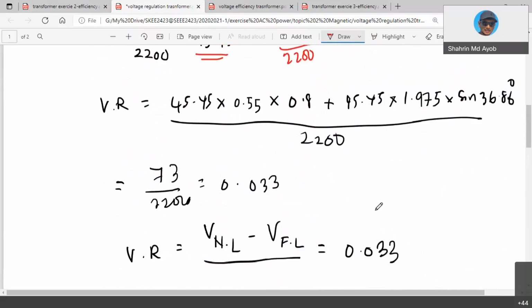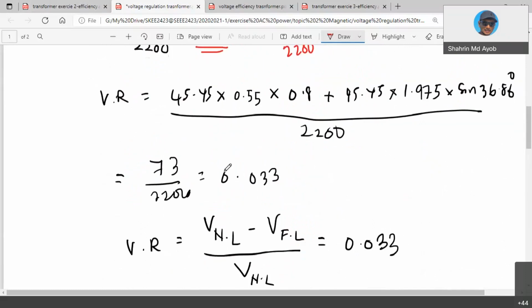So from that, you will obtain that the voltage regulation is around 0.033, which is 3.3%, which is not very good actually. A transformer with very good voltage regulation usually has around 1% or less. Because we want the transformer to have a very minimum voltage drop. If the voltage regulation is big, meaning there are a lot of voltage drop inside the transformer, so losses — we don't want that.